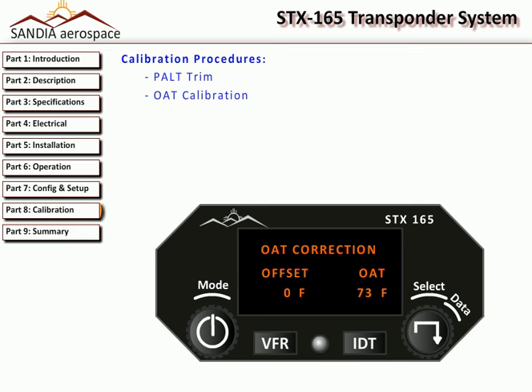Rotate the Data knob to adjust the temperature correction value until the displayed temperature matches the reading on the calibrated temperature sensor you placed next to the OAT probe. When finished, simply press the Enter button to save. A very simple calibration procedure. Just remember to always use a calibrated temperature sensor for adjusting the STX-165's temperature readout.